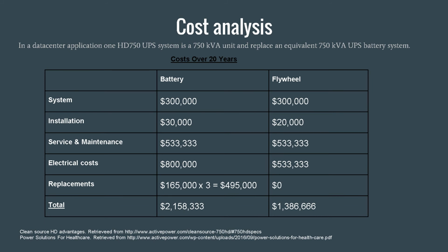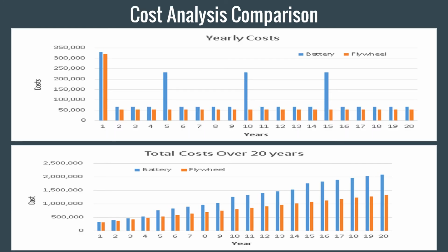For the cost analysis, we analyzed the systems over a 20-year period, considering the cost of the system, installation, service and maintenance, electrical costs, and replacements if necessary. In total, we found the battery cost approximately $2 million, and the flywheel $1.4 million. Plotting these numbers on a chart, we see that the battery accumulates more cost over time, while the inertial system increases linearly.